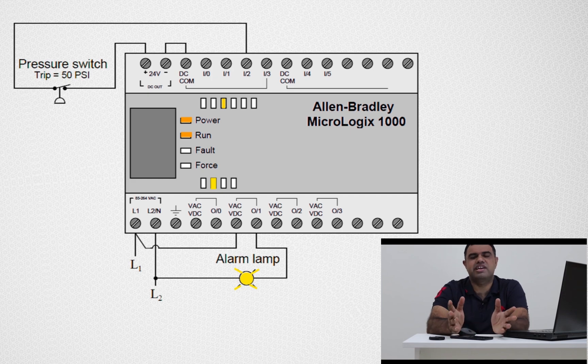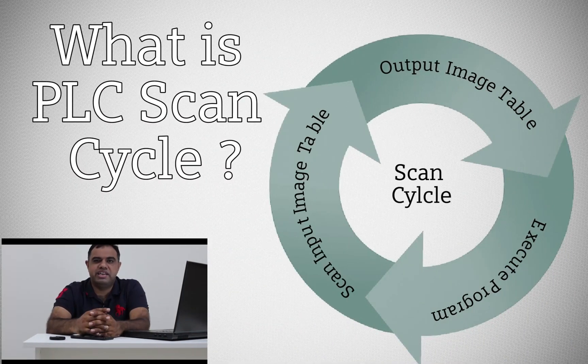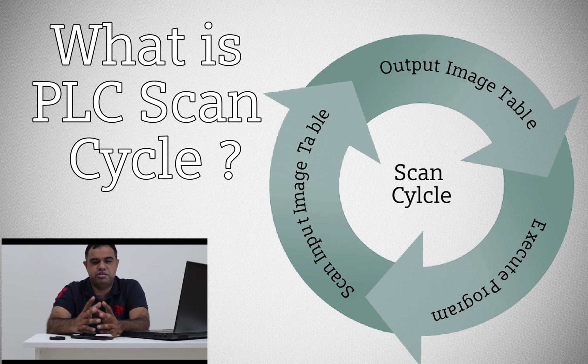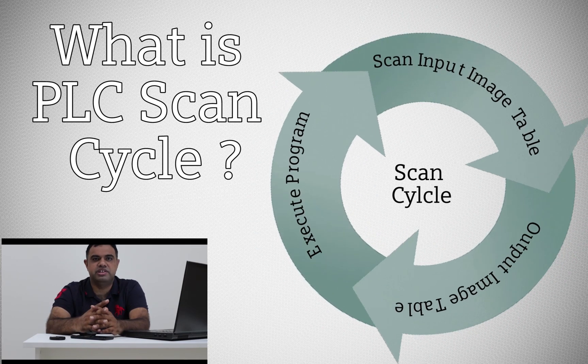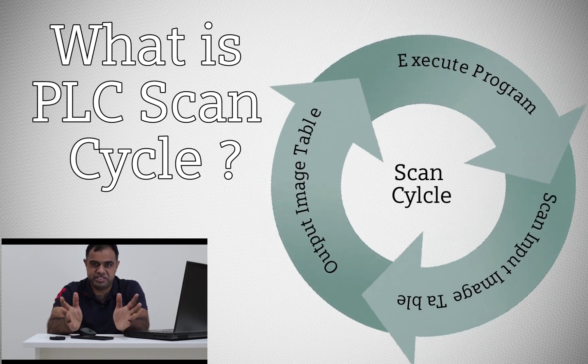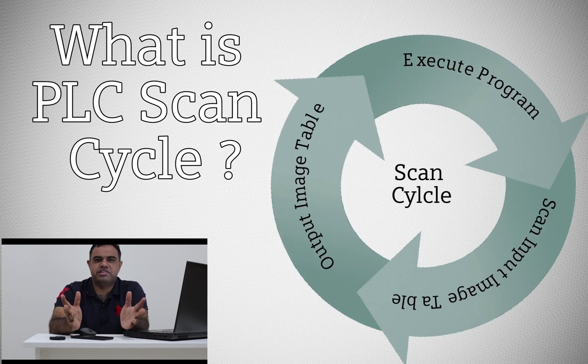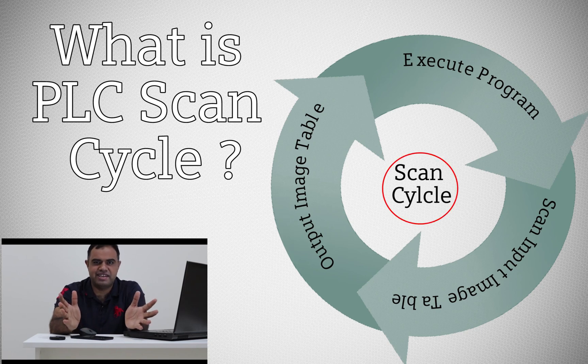The PLC scan sequence consists of three steps: Number one, scan input image data table. Number two, execute program. Number three, update output image table. The time required by the CPU to go through these steps is called PLC scan time.